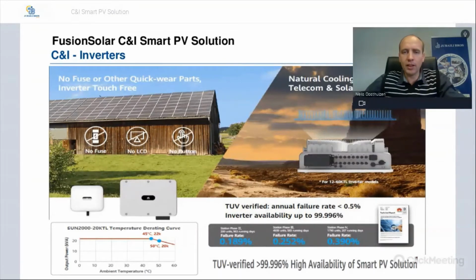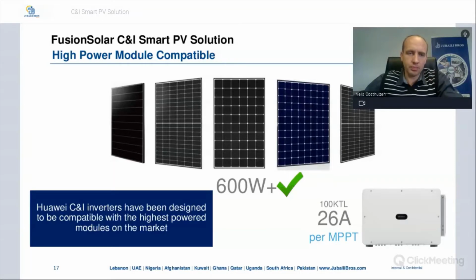Then, as we all know, Huawei actually started as a telecommunications company, but what Huawei has done is they've incorporated the technology or experience they've got on telecommunication towers, and they've shared it with the digital power division, and that has then formed part of the Huawei inverter technology development. So it makes use of natural cooling that's verified by telecom and solar applications. And then it's TUV verified with an annual failure rate of less than 0.5%. Inverter availability is up to 99.996%. So this proves that the inverters are very reliable.